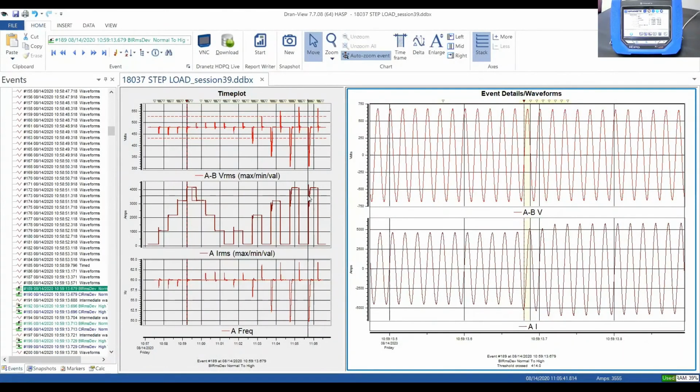As an example here, if you look at this point over here, I'm at 75% load, and you can see my vertical line here. That's my event marker, the event that I have highlighted on the left. You can see these little tick marks here. That's the event that's right here. So I'm marking that event, and that event is the transition from 75 to 100% load. You could see that transition in current right over here. So if I just zoom in real quick, we'll better show that.